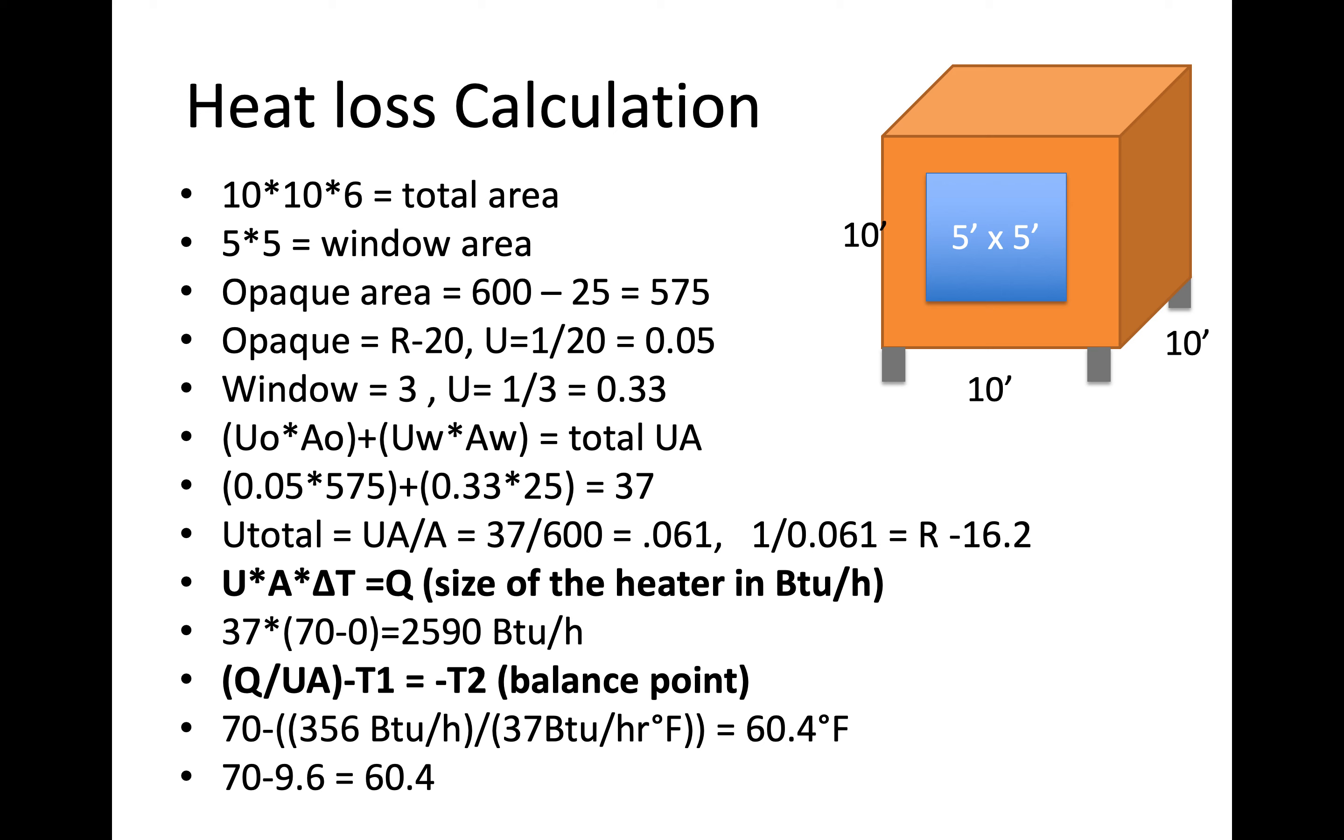So we can calculate the balance point. So that's the temperature outside that would require this person who's giving off 356 BTUs per hour, the temperature outside that would require him to turn on the heater. So we can just rearrange that equation to solve for temperature 2. So we've got q, which we already calculated, divided by the UA. So q is the energy that's available to us from his body. That's the 356 BTUs per hour. And the UA we've calculated earlier, that's 37. And so we can set it up q divided by UA minus temperature 1, which we also know because we know that he's really strict about this 70 degree temperature he requires. So we set that equation up, we're solving for temperature 2, and we get 60.4 degrees Fahrenheit.